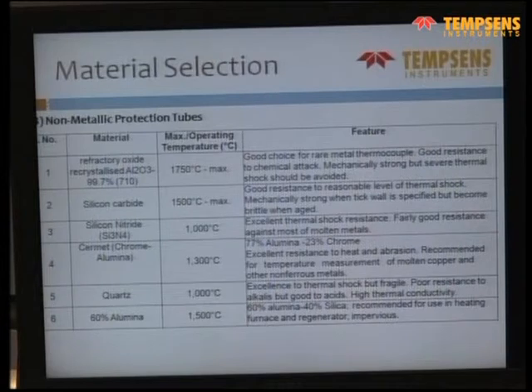Then quartz is for 1000 degrees centigrade, and it is used for acidic application, and it has got good thermal shock resistance. There is also a tube of 60% alumina, which is having good thermal shock resistance. So these all tubes are available, which are mostly ceramic tubes.